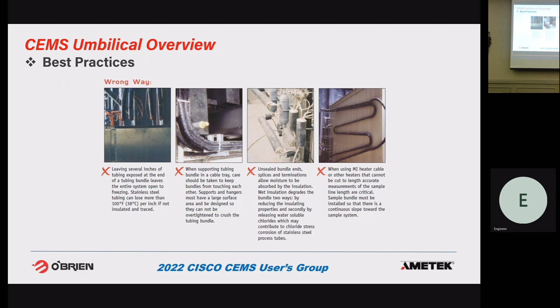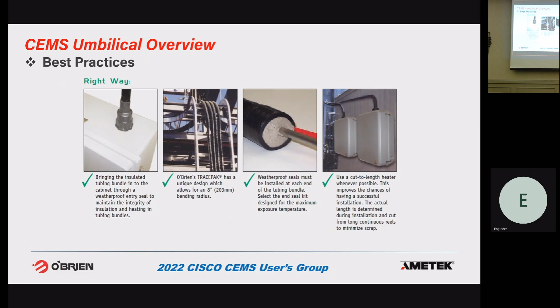This ran, I think, for about a year, and then it plugged. They sent me a picture, and it was pretty obvious what was going on. So if you have a bundle that you can't cut back, if you can reroute it to take up extra distance, or if you have to spirally wrap it around something, have the low point at your equipment, and not in the middle of the line. This one shows bringing a tubing bundle all the way into an enclosure, with nice air gaps in between the bundle, sealing the end of the bundle, and again a downward slope all the way into the enclosure.